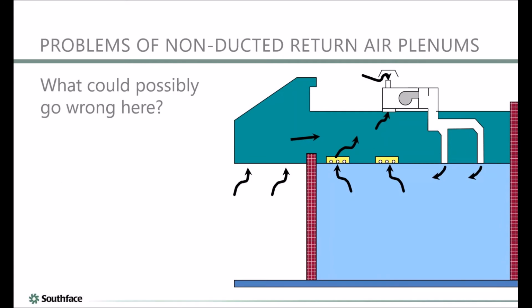Here is an anatomy of a section of a building. This is one of many buildings that I have personally seen that had a problem, and this particular one was a car dealership. It had a rooftop unit, and the supplies went through that plenum space. Above the drop ceiling was the return air plenum, and the light fixtures were ventilated.